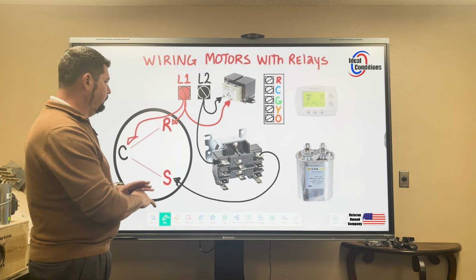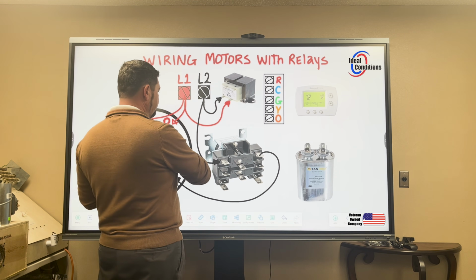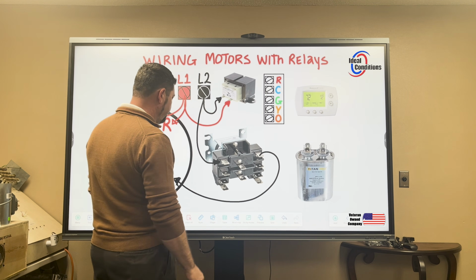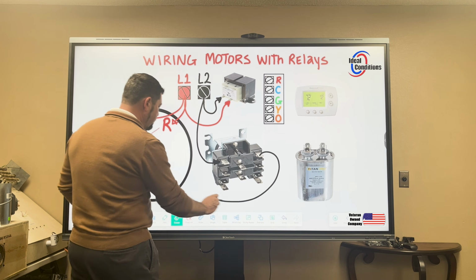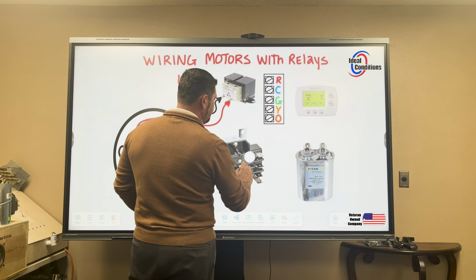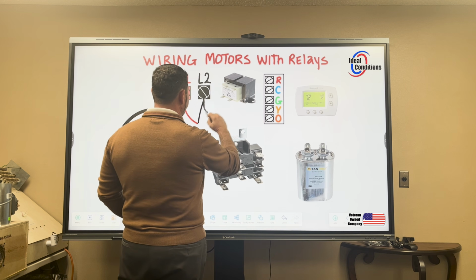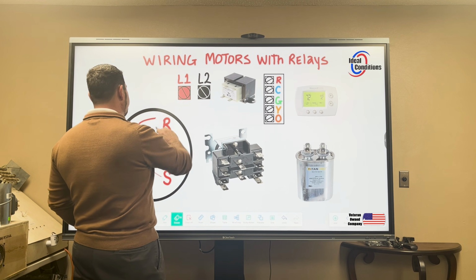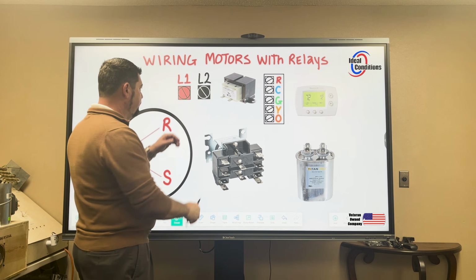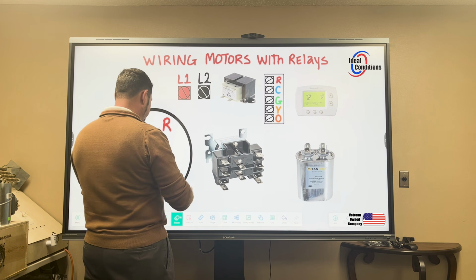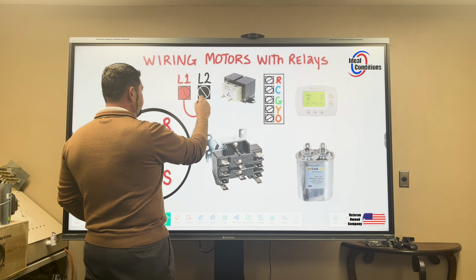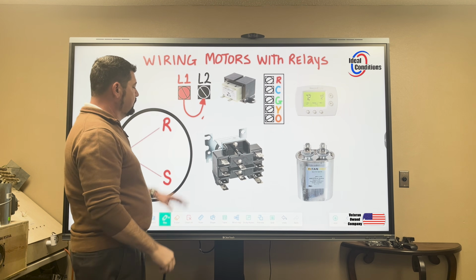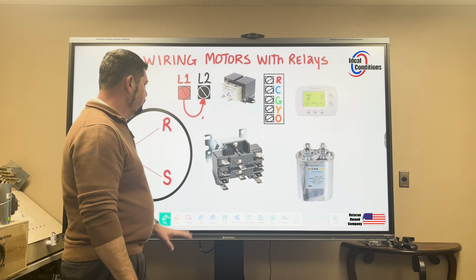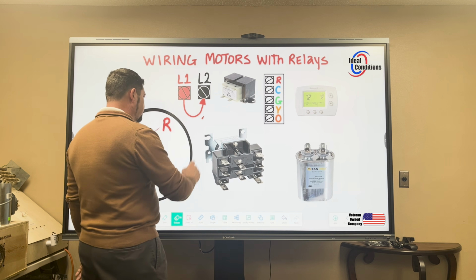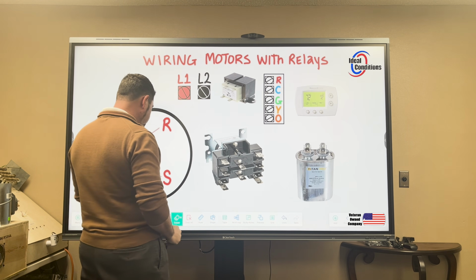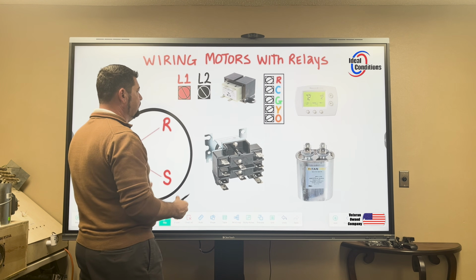So don't work on one leg and then go back to the other. Work on one leg all the way through, and when you think you're done, inspect it and verify it's landed on all the proper terminals. You don't want to butt two legs of power together—even though you're not literally running L1 to L2, the way we just drew it, we did. So be very careful to finish one leg, inspect it, and make sure that leg is complete.